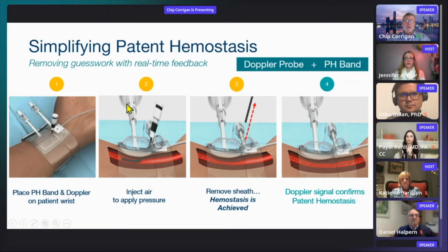What we actually do is we inject 15 cc's of air in the second picture. This actually is more of a tourniquet type of thing at this point, which we completely occlude the vessel below. We then pull the sheath out, and you can see we still have occlusion, but at this point you have hemostasis, just like all the other bands. In slide 4, which really differentiates us from the others, we start releasing air slowly until the vessel opens up.